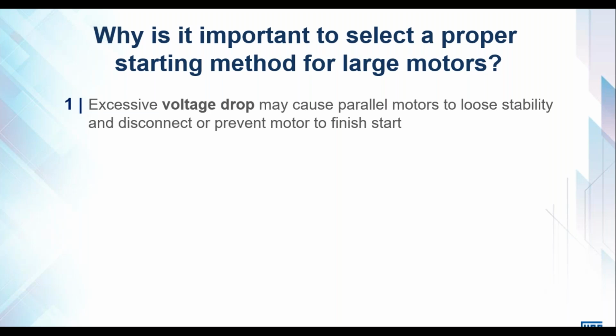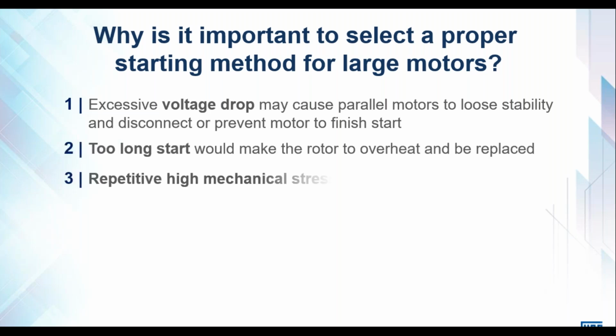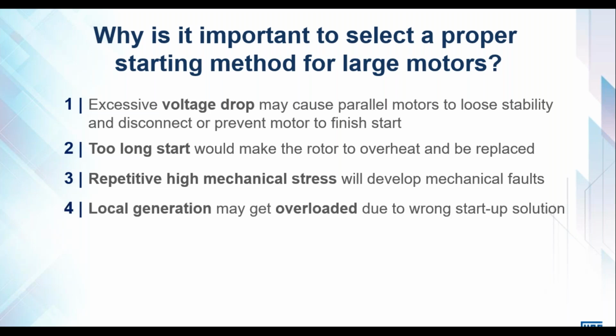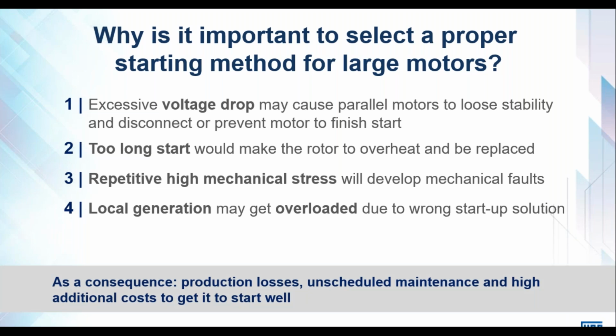Also, when a large motor starts on a plant, you can induce a voltage drop on other machines and loads on the grid, on the plant at least. Prolonged start can cause the rotor to overheat, so you need to examine the thermal capability or the thermal limit of the machine. And then multiple direct online starts can develop a high mechanical stress, so it's something that needs to be taken into consideration. And then overload of local generation. This talks to the power supply issue for the plant.